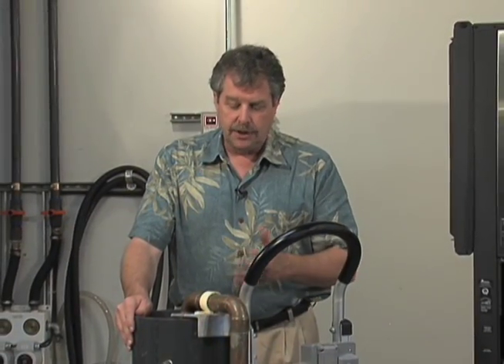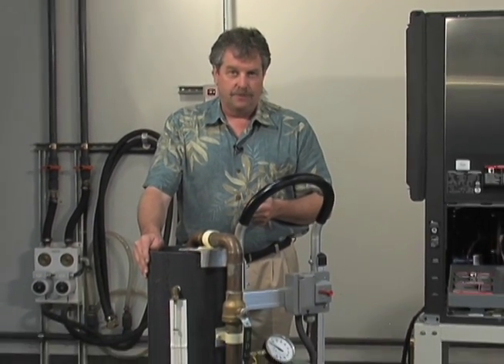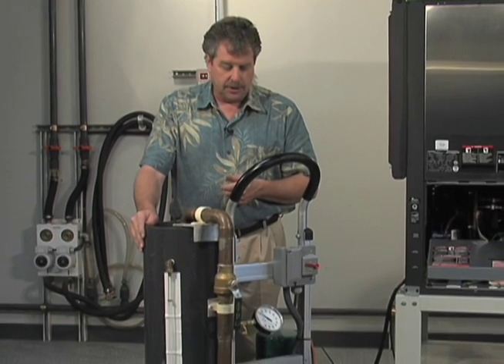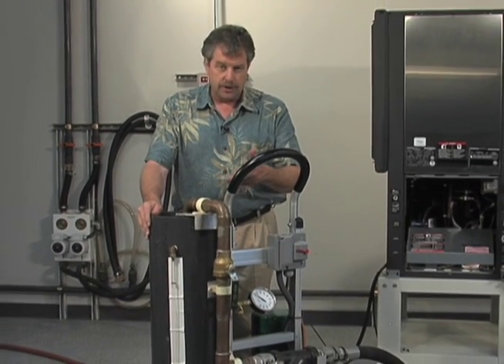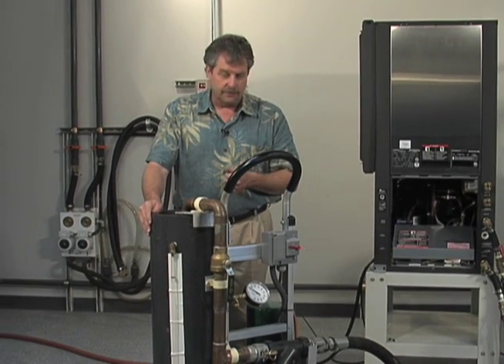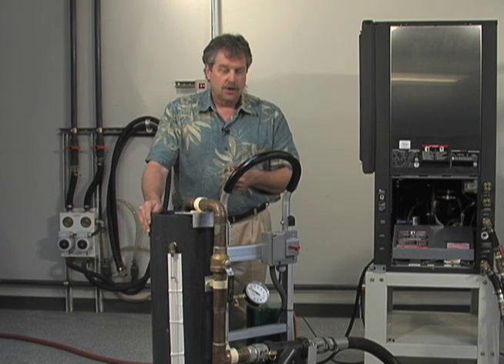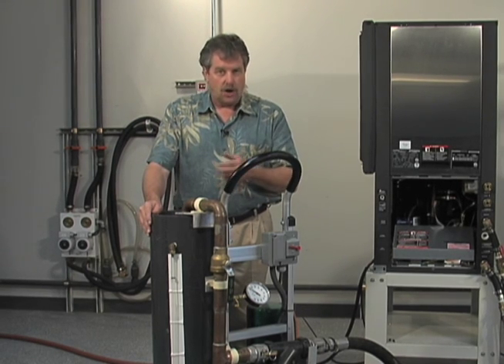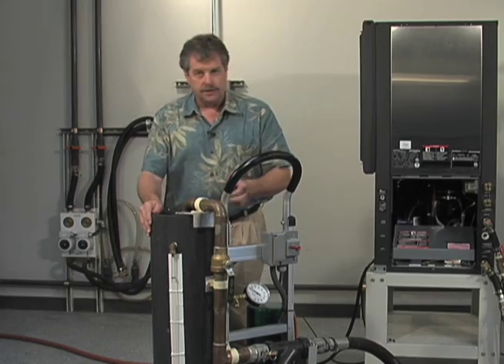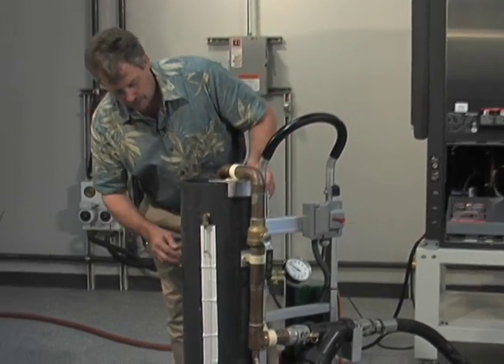So now we've been circulating the fluid through both the heat pump and the loop field for a while. We see no bubbles, no indications of any air in the system, so we're going to verify that. Again, we've done several deadheading procedures. So we're going to reset our indicator on our sight glass to the water level inside our reservoir.